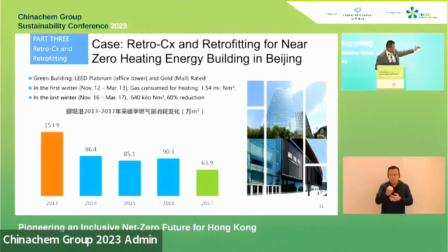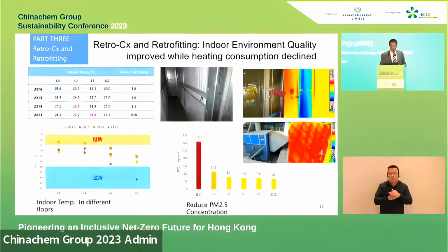Going into detail, after 5 years, for the whole winter with about 125 days of space heating, the natural gas consumption reduced from 1.5 to 0.64, a 60% reduction. No one believed that, since it's already a very good building with a lot of ratings. But after commissioning and retrofitting, we made it happen.